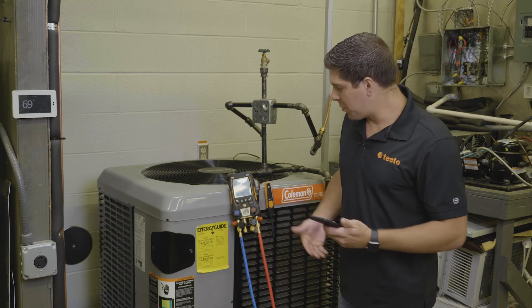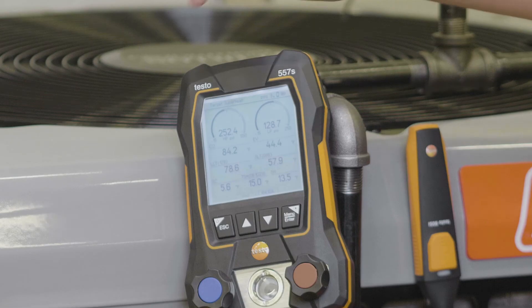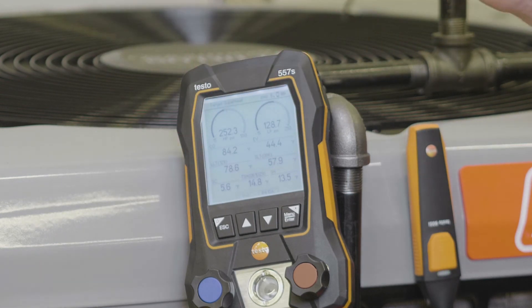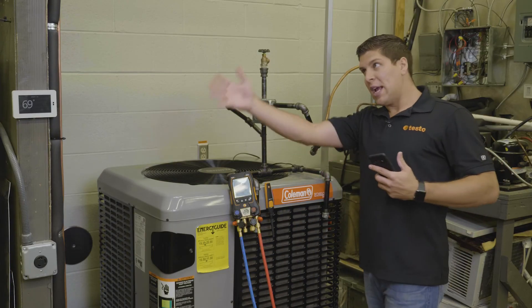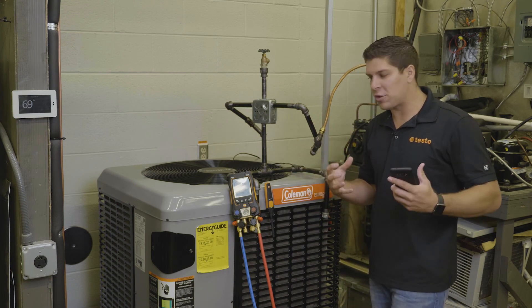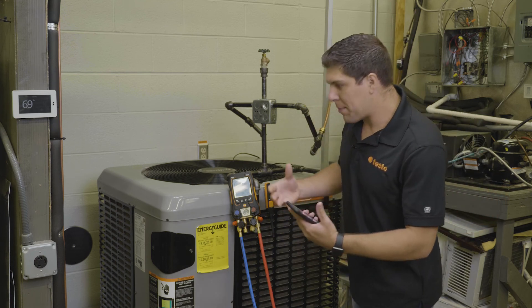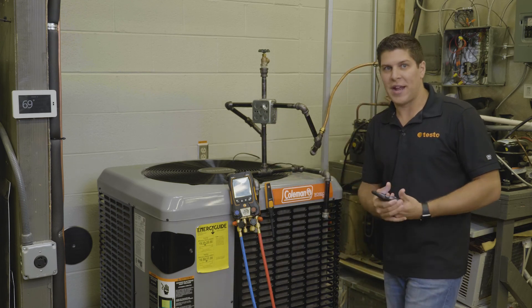Right here I can see my target superheat is at about 14.9, because we're taking our condenser and evaporator temperatures — our suction and liquid line temperatures — which are giving us our subcooling and superheat. With the 605i's and the airflow within the units, we're also getting all those details and measurements on the device where it's doing the calculations for you, as well as on the app and in your hand.